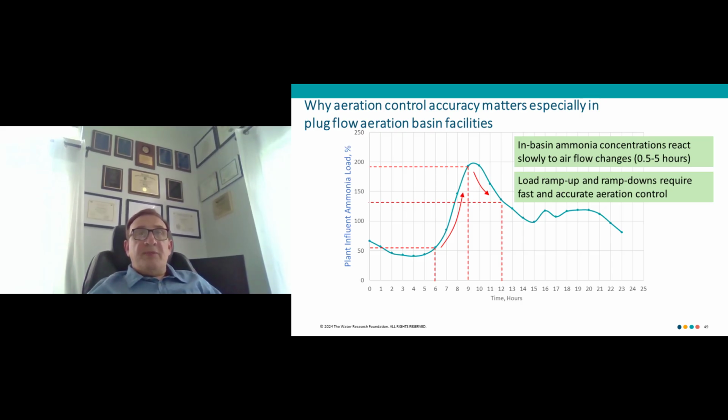So it can be easily concluded that a quadrupling ammonia load and a long reaction of ammonia concentration to airflow change require a more advanced control method, because PID, as we could see, didn't provide the required accuracy.